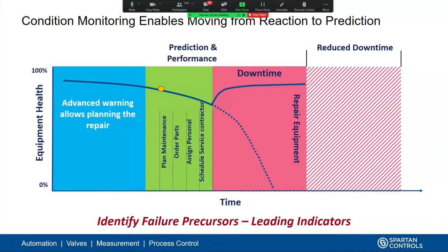Now, maybe some of the other things that we didn't think about is what is the impact on the performance of that pump? As we showed, as that fault increases, the actual equipment health and therefore efficiency of that pump is going to decrease. It's not going to be able to move as much fluid for the same speed. In a lot of applications, we've got VFDs that are maintaining flow through the system.